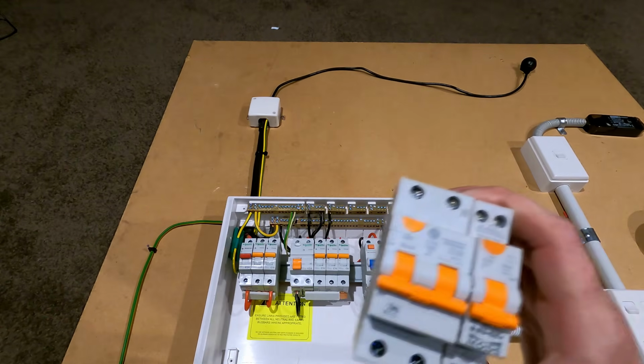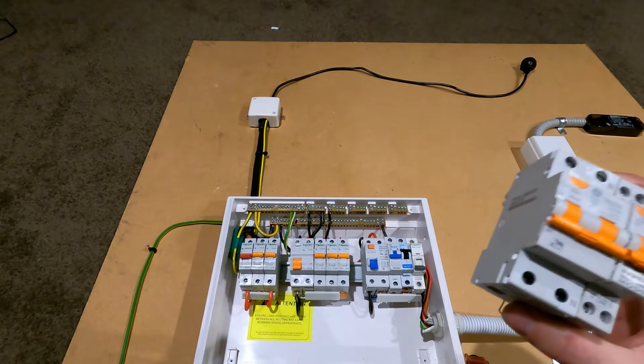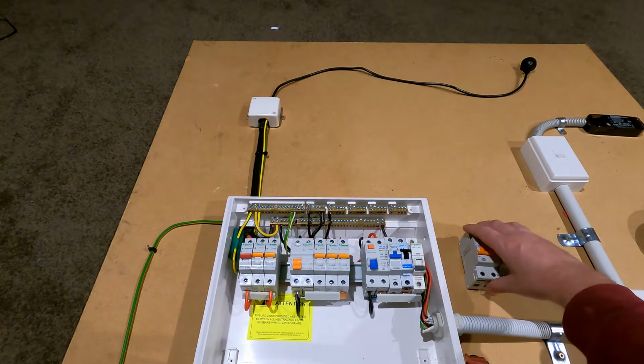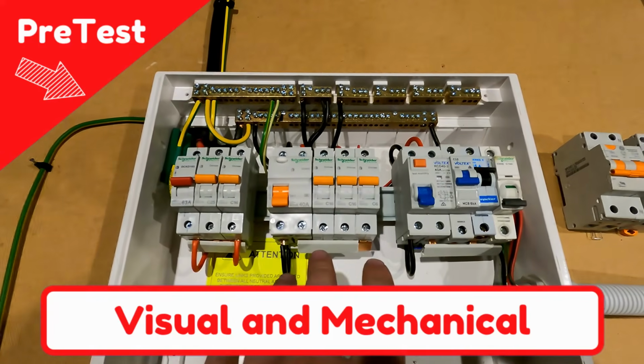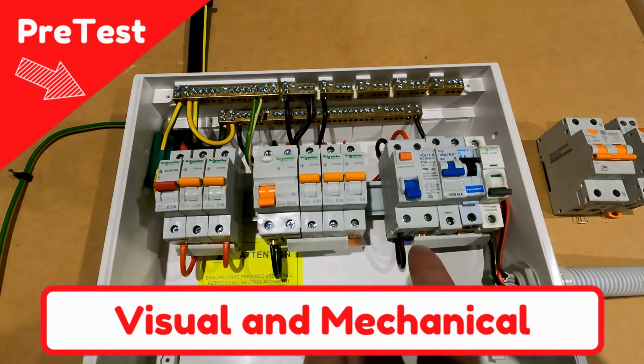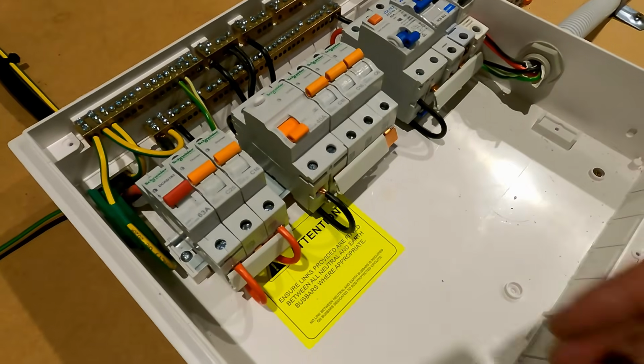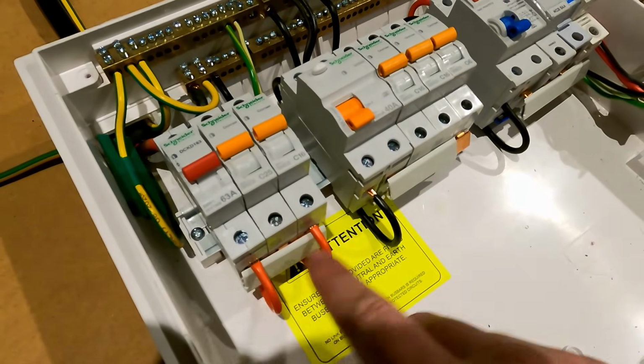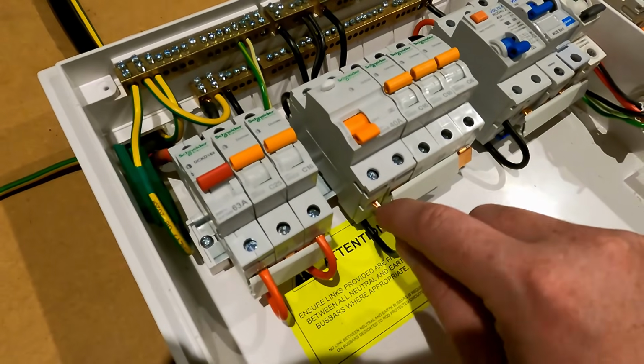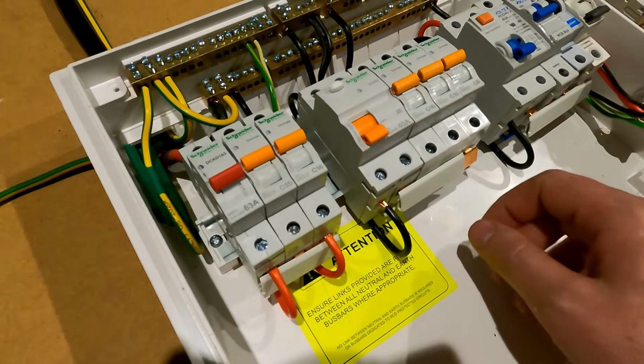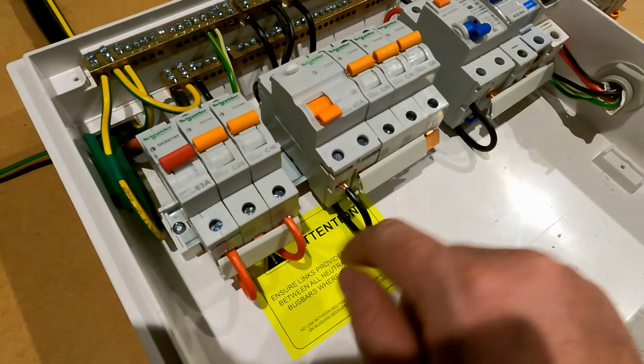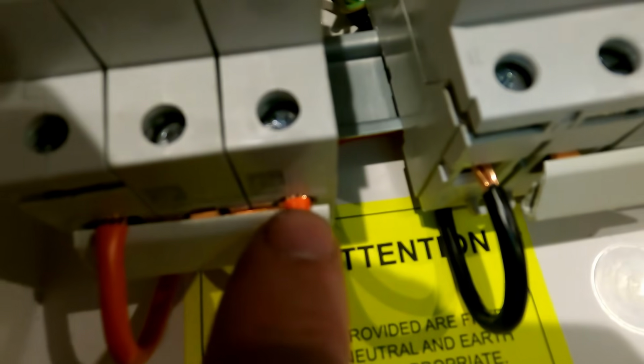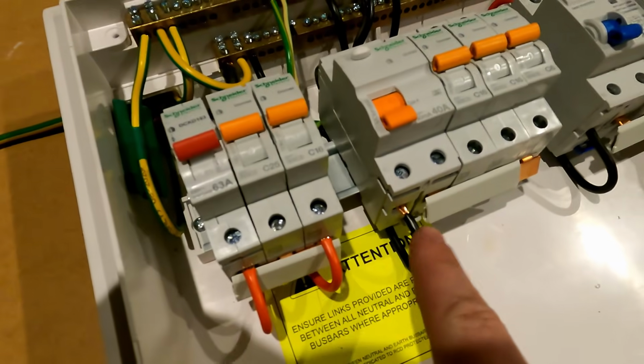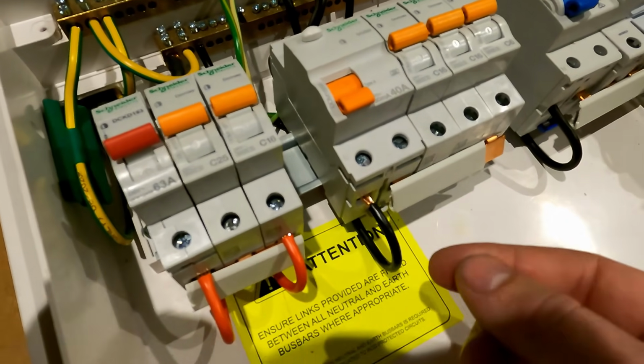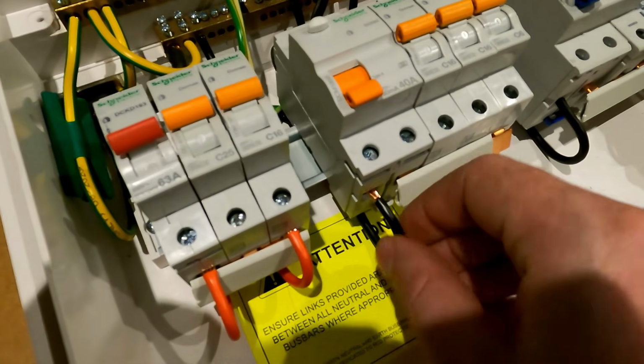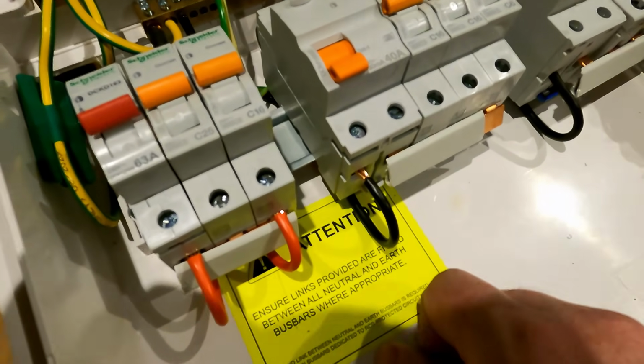I will be wiring one of these into the switchboard when I remove some of these components for our live testing after. So the first things you want to go looking at in the switchboard are purely visual and mechanical things. So things to look out for are your bare conductors hanging out of these terminals. What you want to do is have the insulation flush up to the plastic here. Not so that the clamp is touching the insulation, but very similar to this one. That one there is good, this one there is not. So what we'll do is we'll pull that out, we'll trim it down, and we'll clamp it back in there so the insulation is flush with the edge of that.